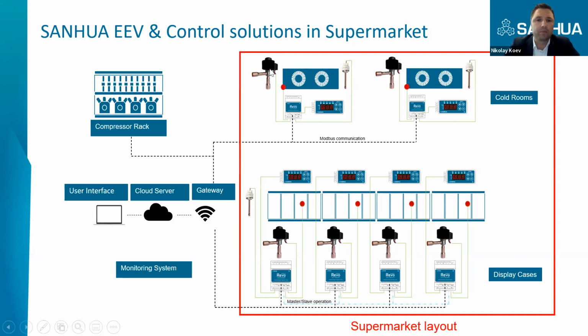Then we have the electronic expansion valve, the pressure sensor, and the temperature sensor installed in the evaporator. These controllers can be connected via Modbus. And for the cabinets, again, the controller can be installed in the switchboard on the top of the cabinet, and the display can be installed in some visible and accessible place for the technician to change the parameters, but also for the supermarket manager, for example, to check the temperature.